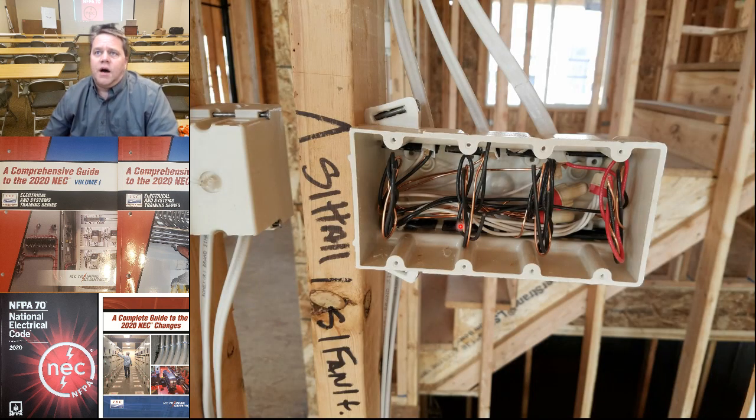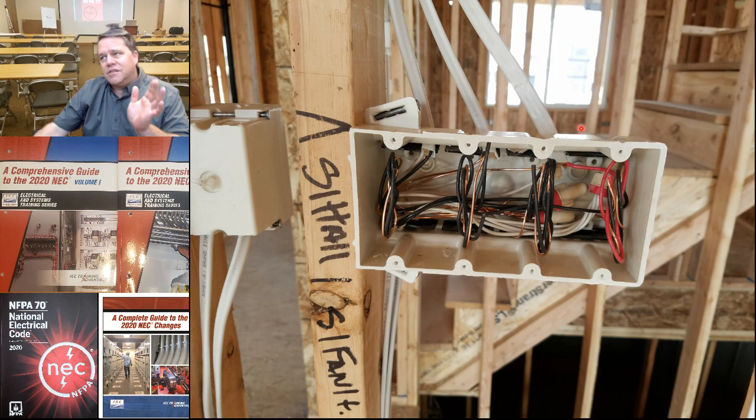So looking at this box here, I have a home run down at the bottom. So that's the black and the white, and I've got 4 switches that are all on the same circuit. Okay, so I've got one hot that comes in and its neutral in the cable. So in that NM cable, that's 2 current carrying conductors. For these first 3 switches, I've got the switch leg leaving and the neutral going with it. So 2, 2, and 2. Now, bear in mind, it doesn't matter how many current carrying conductors I have in the box. We're just talking about in the cable.